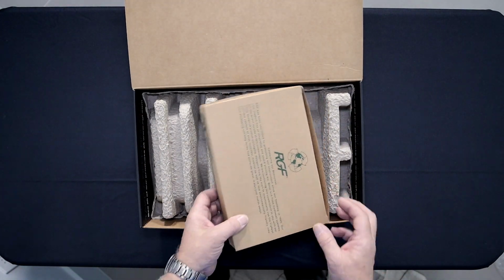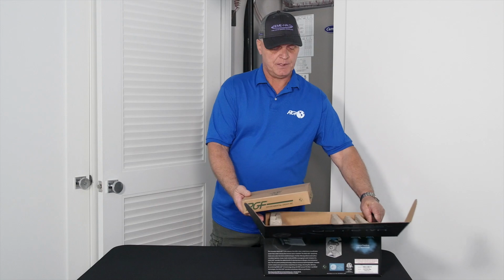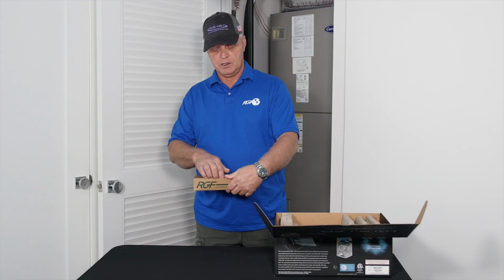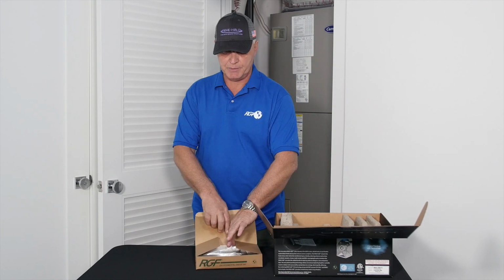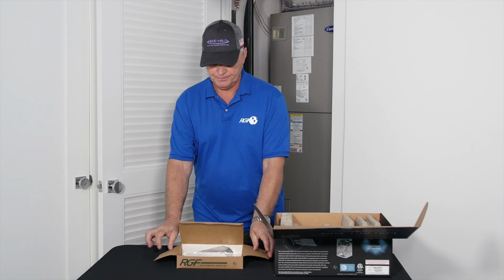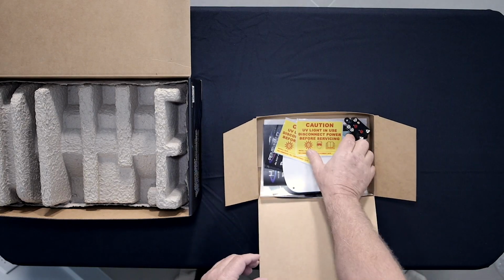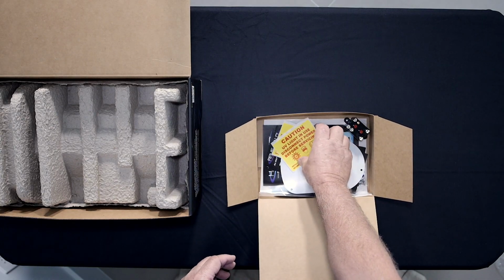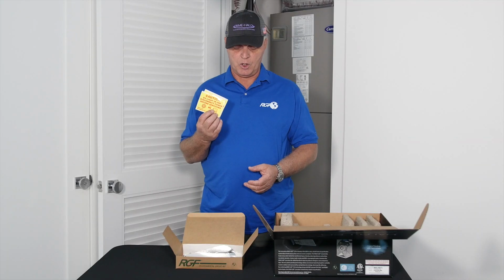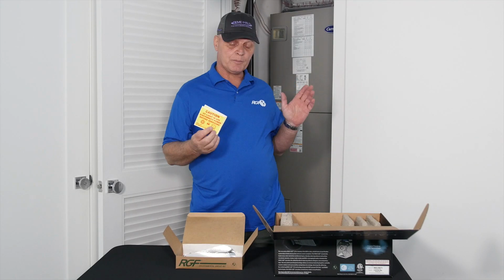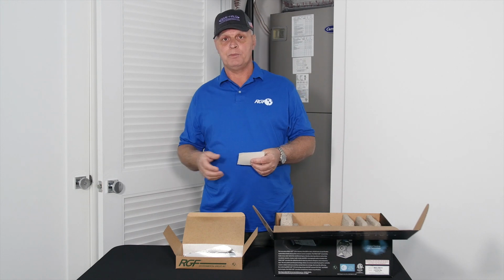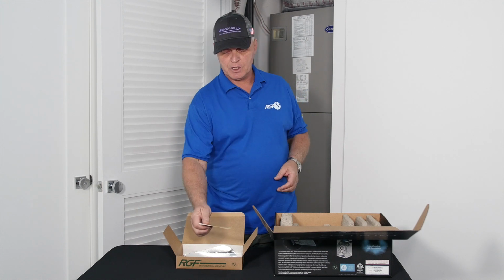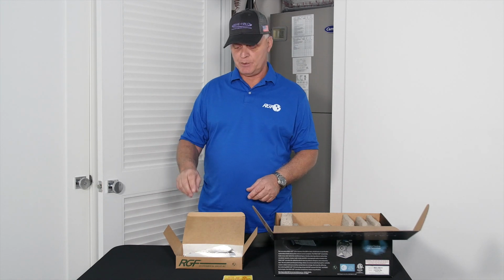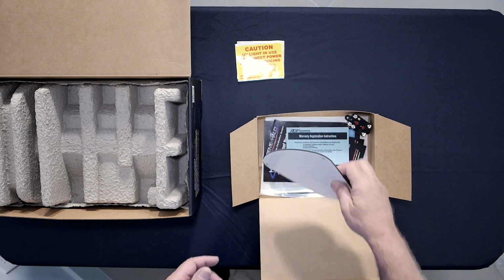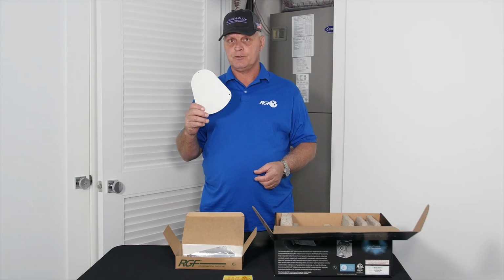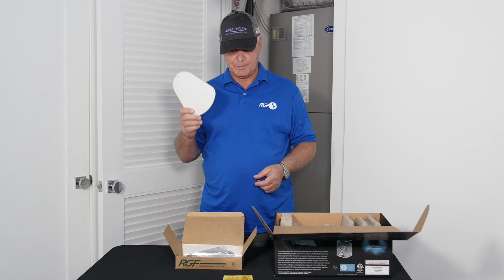First, on the top, you're going to find your accessory kit. This is going to include all of the stuff that you're going to be using when you do the install. As we see right on the top, we have a pair of UV light stickers. These are to be put on your air handler to inform anyone who happens to open it that the power must be turned off because the UV light is damaging to your eyes. Next, we have the gasket for the halo itself, the REMI LED halo.